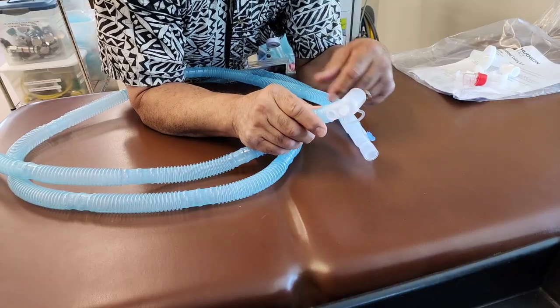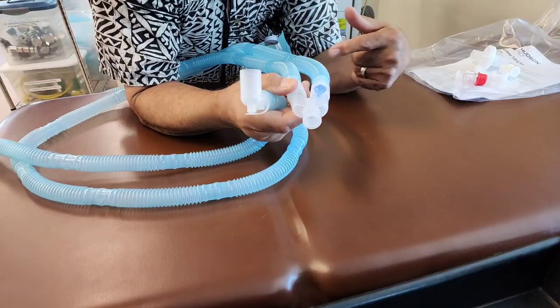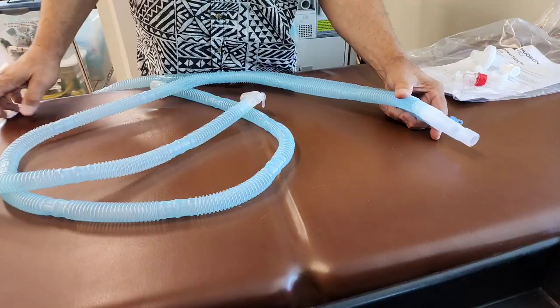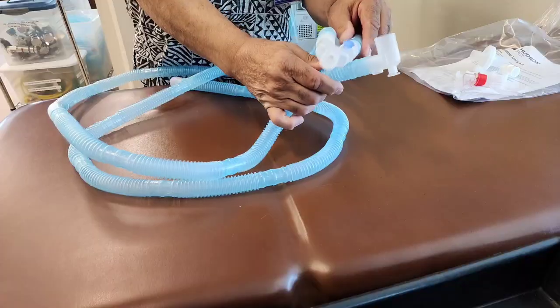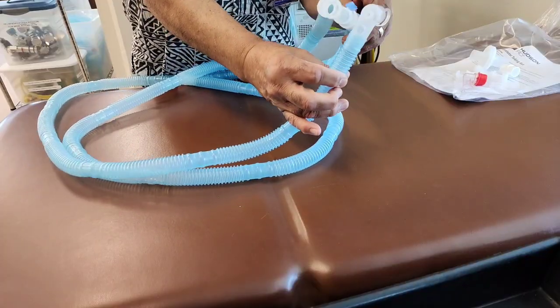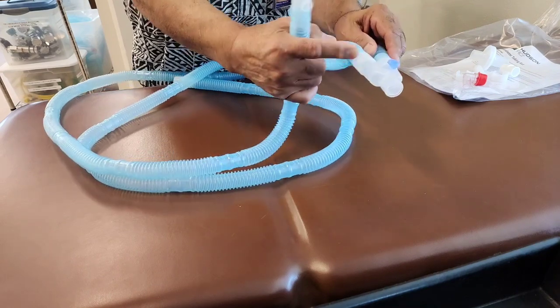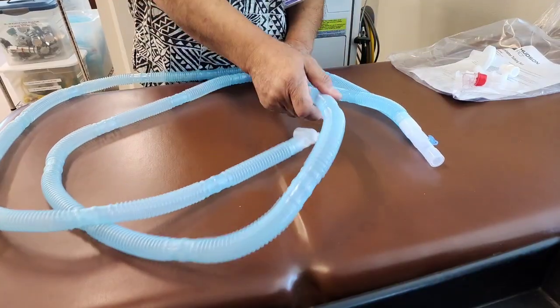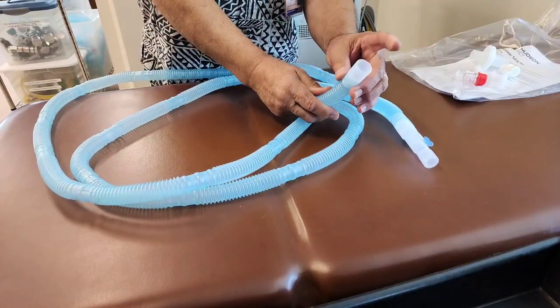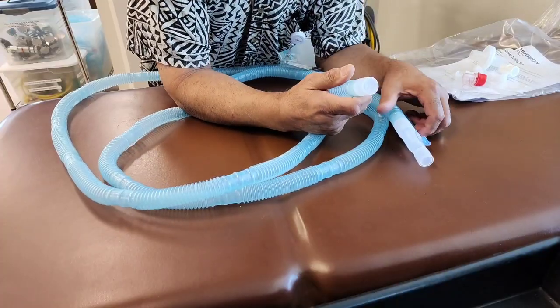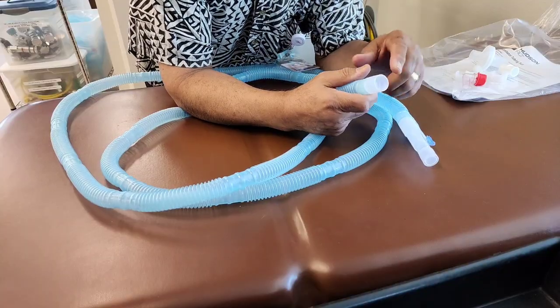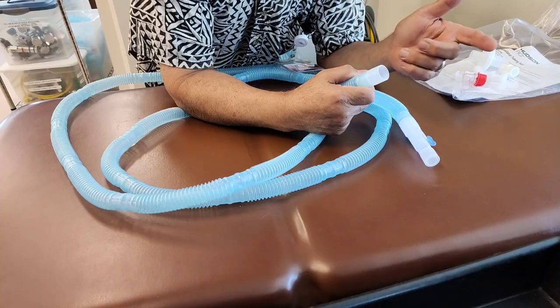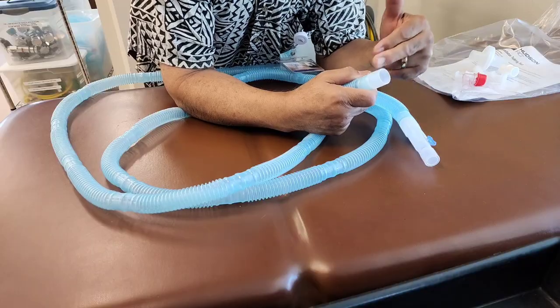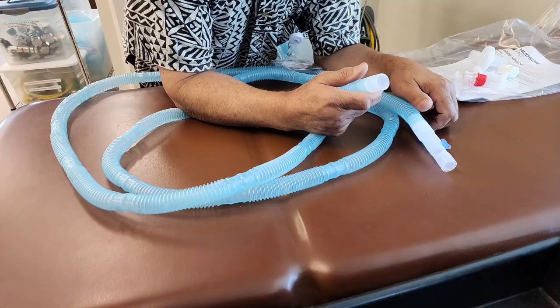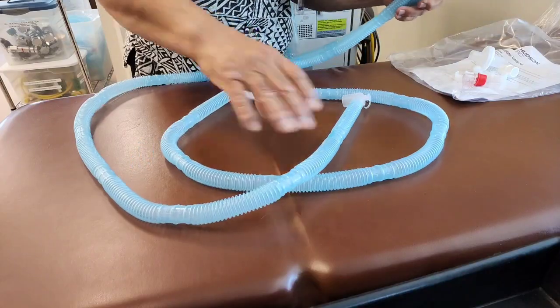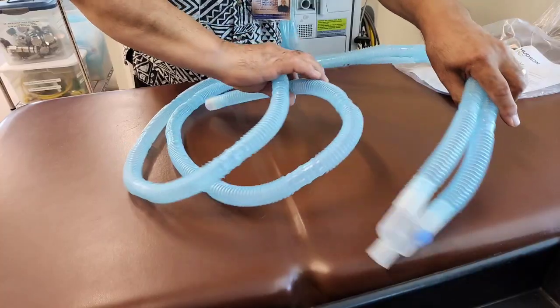So this here connects out from the ventilator to the patient. This is the inspiratory side. If you followed it, these two will actually be the same part, the inspiratory limb. The other end is the expiratory limb, and that goes all the way out from the patient, who exhales, and it comes to this end here, and this will connect to the exhalation port on the ventilator. So it'll also measure the volume. The ventilator will measure the volume of air that's being returned from the patient after being ventilated. Okay, so this is the circuit. It's all like one long tubing.